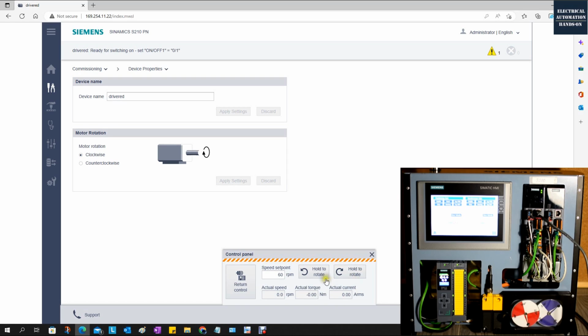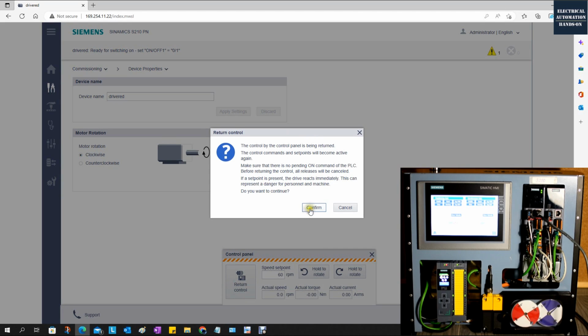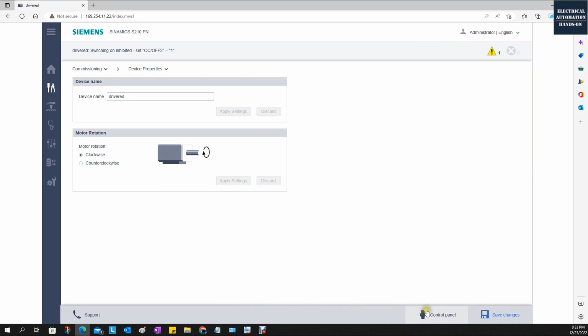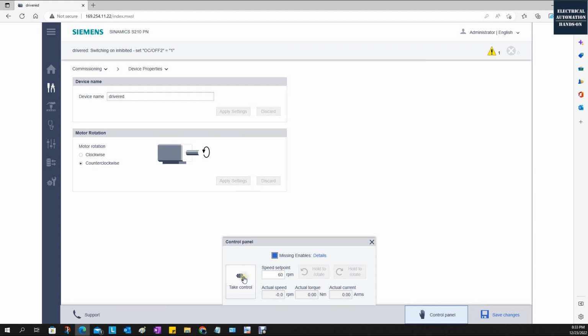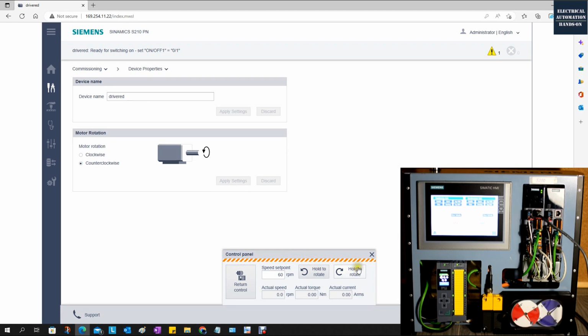Okay, release. And now let's click this backward. In the meantime, we can count the speed. It is running 60 RPM, 1 second, 1 revolution. And if I'm holding this backward, you will see the actual speed is minus. That means the direction. Okay? If I return the control, if now I close this control panel, reverse this direction, apply, and go to the panel again, take over the control, and then this time let's hold this forward. So we will see the motor direction will be backward. Okay, this is the hardware-wise reversed motor direction.